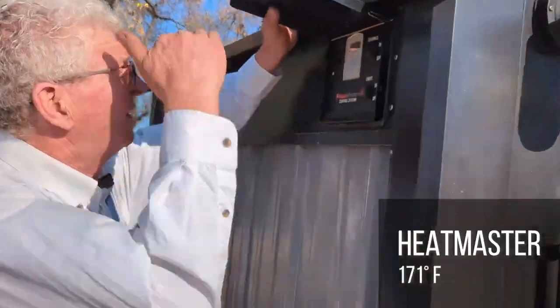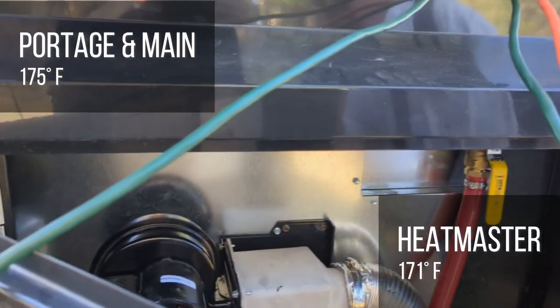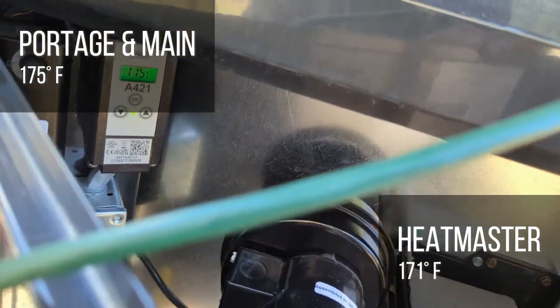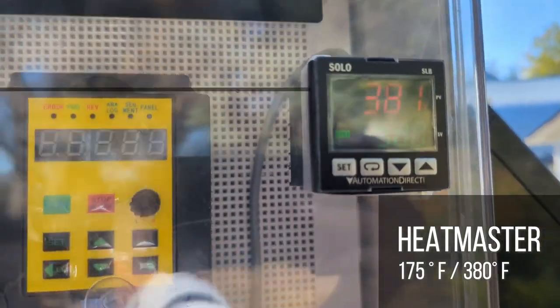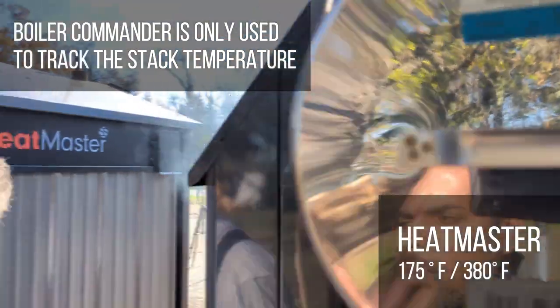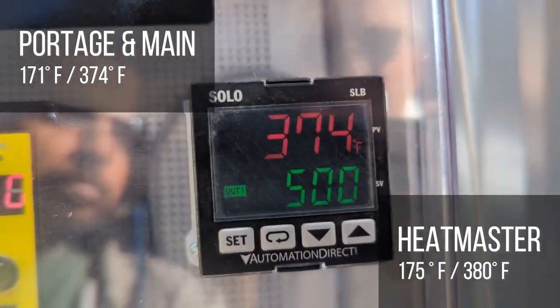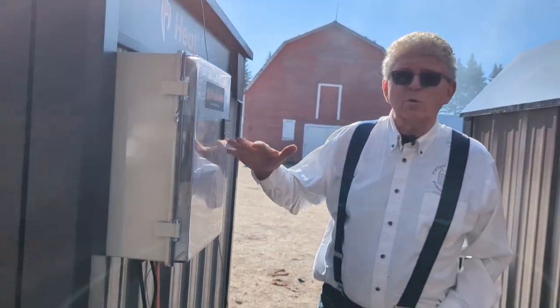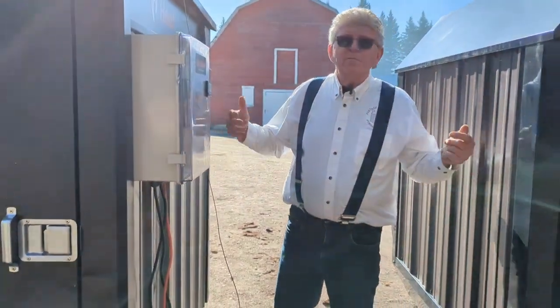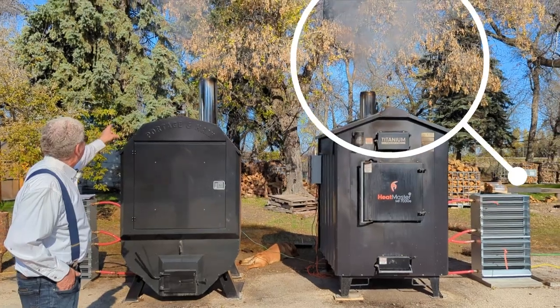The temperature of this boiler is 171 degrees and the other is at 175, rising quickly — they were both equal just a few minutes ago. The stack temperature here is 380 degrees, and this one is at 374 degrees at the moment. The Portage & Main seems to be cleaning up a little bit better right now. We're going to adjust the heat load to match heat burning as continuously as possible.